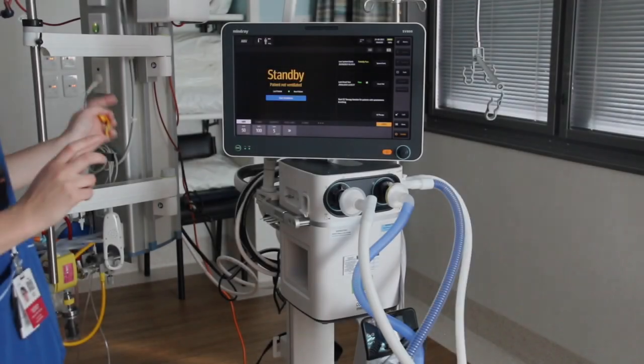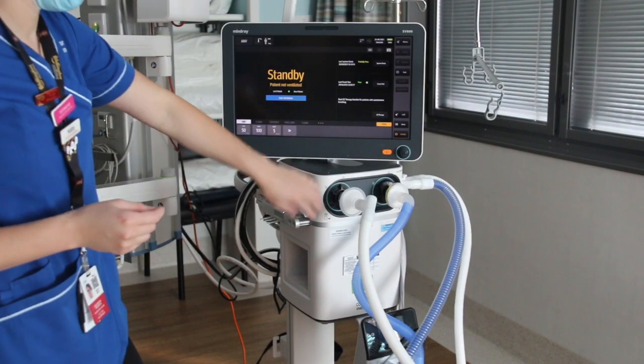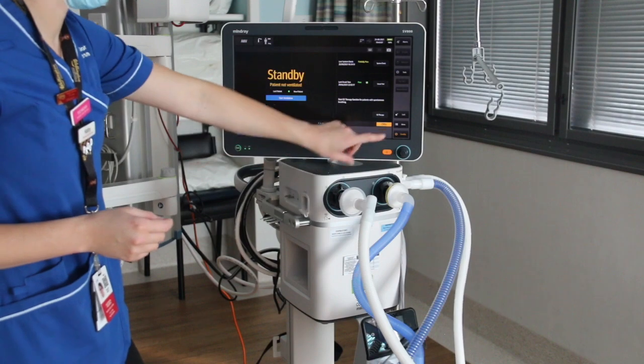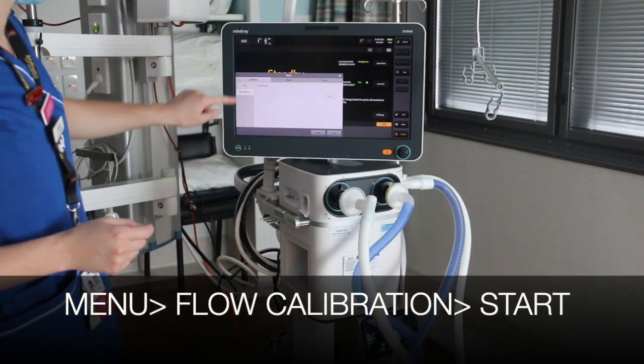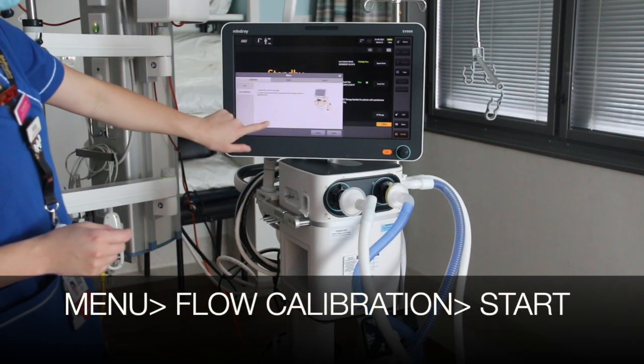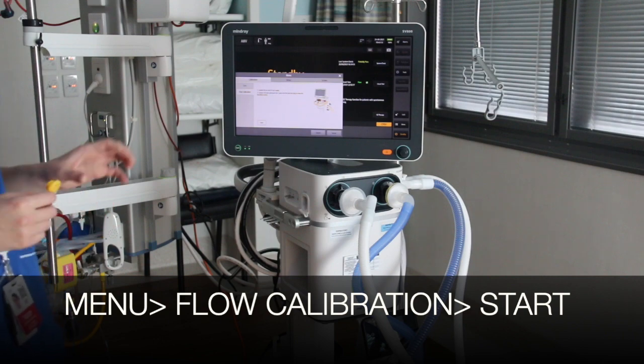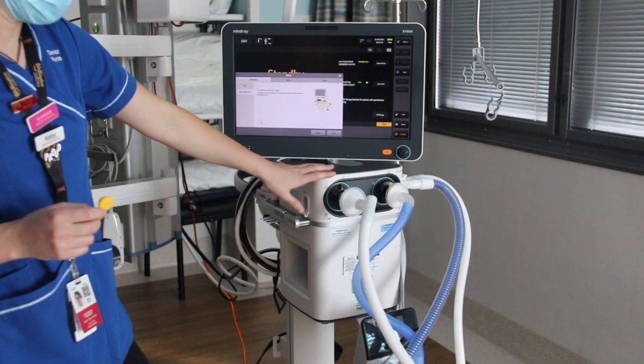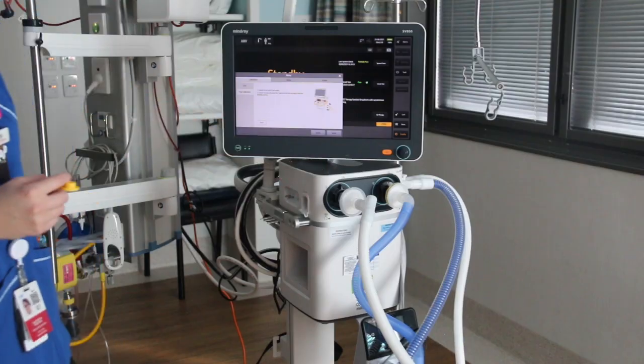The very first thing that you want to do is, from the main screen, calibrate that flow sensor like we talked about. So you're going into menu, flow calibration, and hitting start there. That's your first check to marry up the flow sensor with the ventilator, and it takes about 4 minutes and is quite noisy.